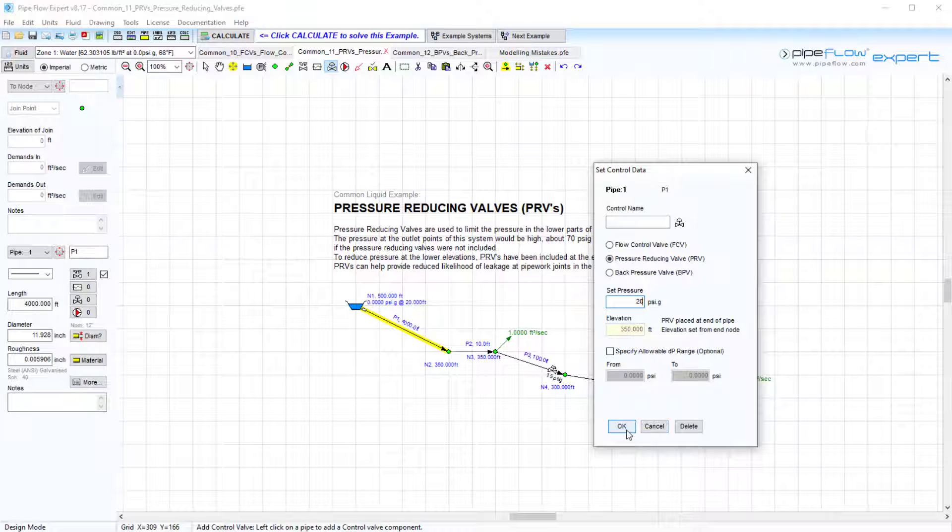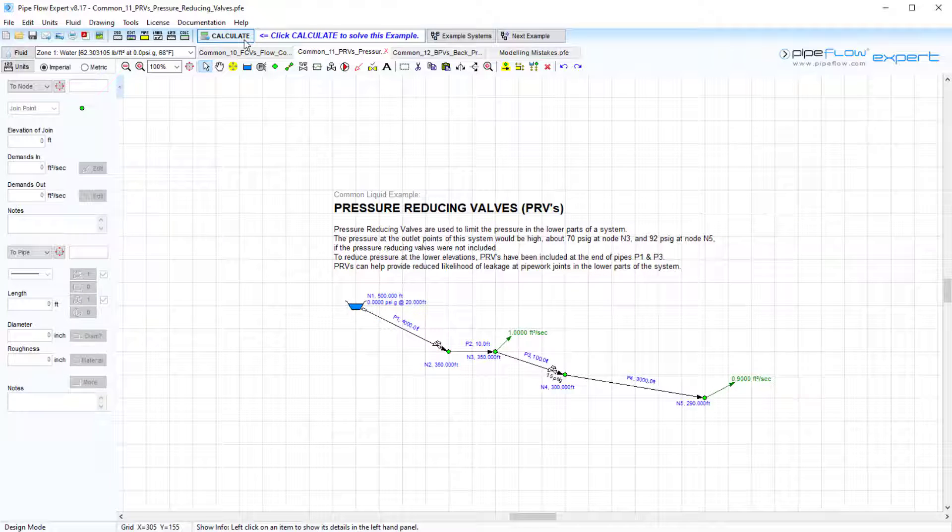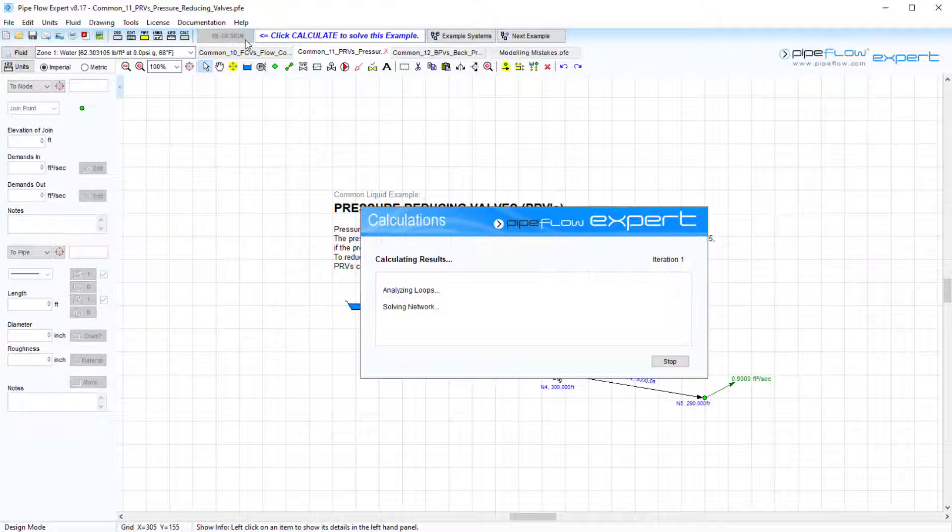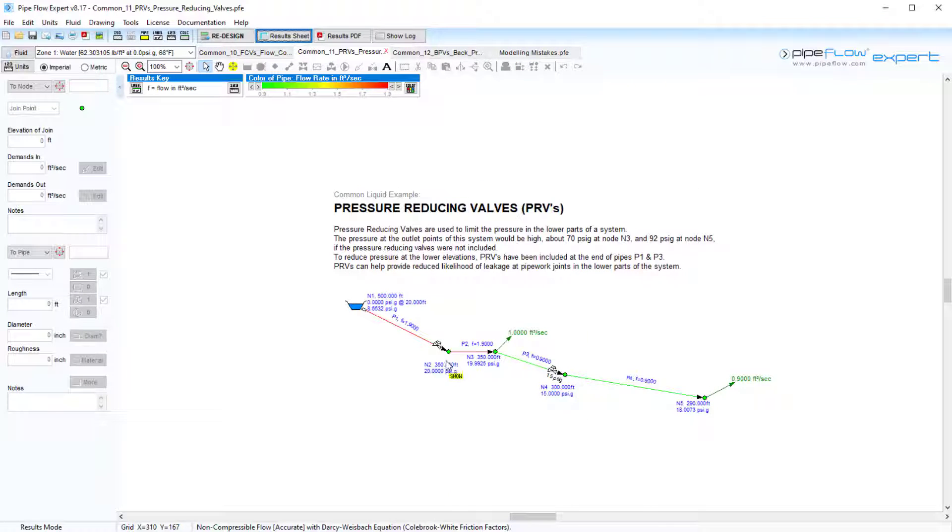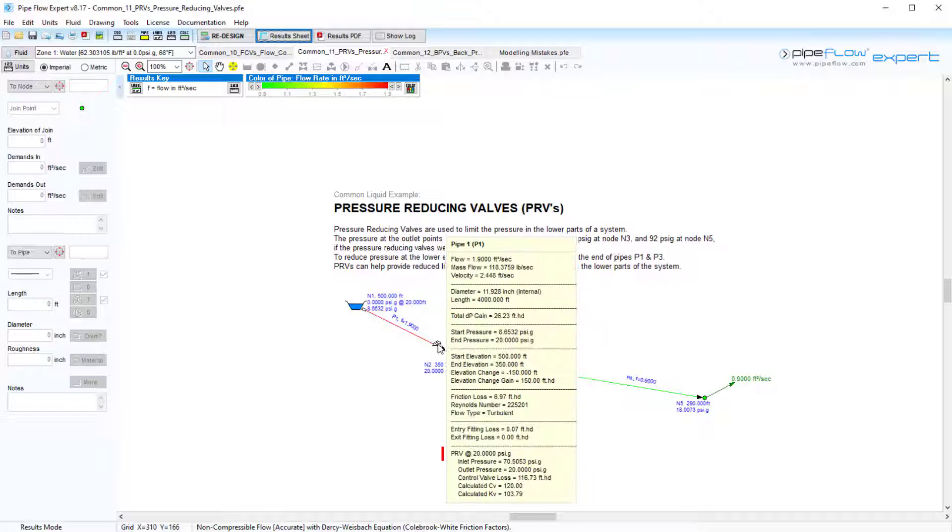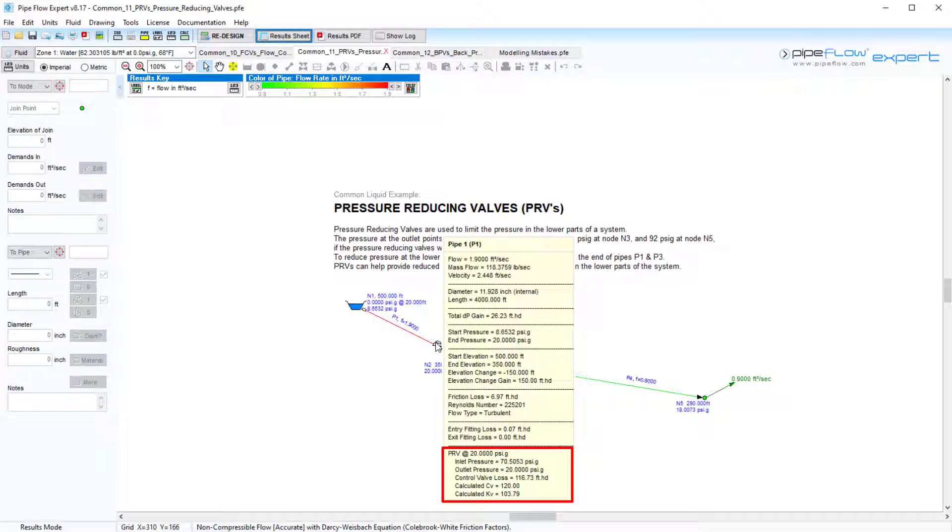Again, we can solve the system and hover over node 2 to see that the pressure has now been reduced to 20 psi gauge, and the valve has added a pressure loss of 116.73 feet of head to limit the pressure at this point.